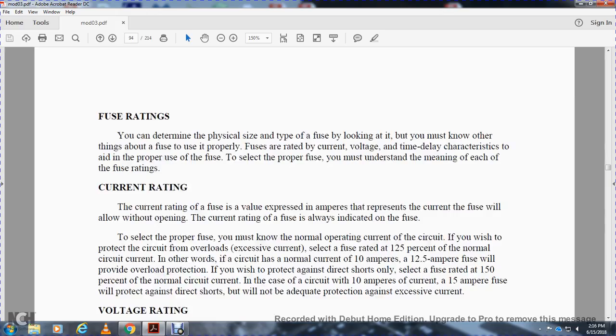Fuse ratings. You can determine the physical size and type of a fuse by looking at it, but you must know other things about the fuse. Fuses are rated in current, voltage, and time-delay characteristics for proper use. You must know the meaning of each of the fuse ratings. The current rating of a fuse is the value in amperes of current the fuse will carry without opening. The current rating of the fuse is always indicated on the fuse. Select the proper fuse for the operating current of the circuit. If you wish to protect the circuit from overload and excessive current, select a fuse rated at 125% of the normal circuit current.